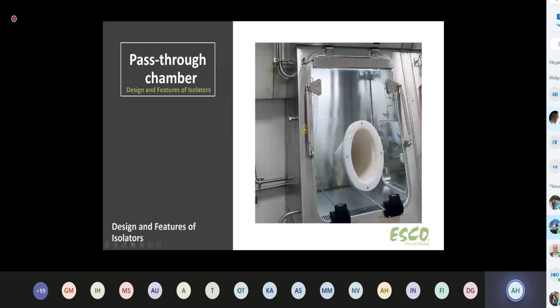It is customizable. Okay. For the glove leak tester, I want to show you that this is actually a more elegant way to mount it on the isolator body. Here you have now a concept of BioVap. Now BioVap is ESCO's bio-decontamination system using H2O2 gassing. So there will be a H2O2 chemical stored here, and the gassing is all automated, controlled by this PLC. So when we have H2O2, it is important to remove the H2O2 safely. We use a catalyst. Okay, the catalyst is called in our language a catalytic converter.